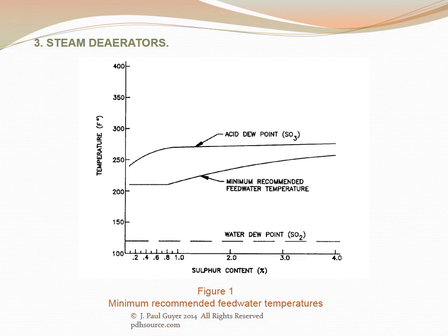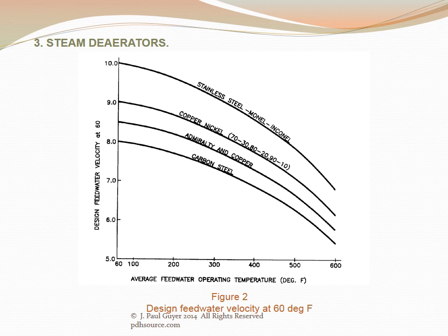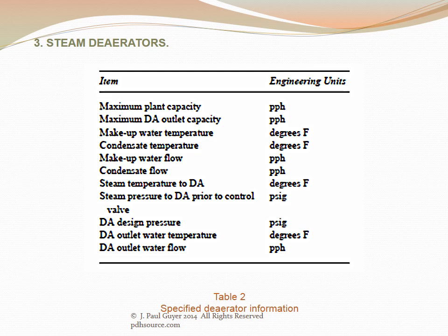Figure one indicates the minimum recommended feed water temperatures, with sulfur content on the horizontal axis and temperature on the vertical axis. Figure two indicates design feed water velocity at 60 degrees Fahrenheit, with average feed water operating temperature on the horizontal axis. Table two indicates specified deaerator information including maximum plant capacity, maximum deaerator outlet capacity, make-up water temperature, condensate temperature, make-up water flow, condensate flow, steam temperature to the deaerator, steam pressure to the deaerator prior to control valve, deaerator design pressure, deaerator outlet water temperature, and deaerator outlet water flow.